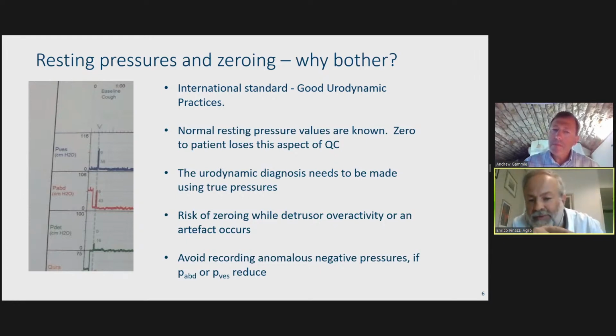Another point is that when you zero to the real initial pressures, if you have a decrease in pressures in one of the two lines, it will be much easier to recognize than if you zero both lines at the beginning. And so you start from 0 in the bladder, 0 in the abdominal, and then you go to a negative value in one of the two lines. It will be much more difficult to understand. And when you go to a negative value, we will have an addition. We will put, for instance, the P-abd value over the P-ves value. We will have the sum of the two, and this will change the final results of your investigation.